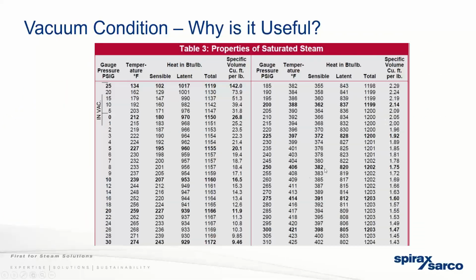So vacuum condition, why is this useful? So here's a steam table. It's going from vacuum up to 30 PSI. The table would look pretty similar even if we went up to 150 PSI. The latent heat is the energy used for heat transfer in the steam. The higher the pressure, the lower the energy, so the lower the latent heat. And you can see as you go into vacuum, it continually increases. So at 20 inches of vacuum, we have around 1,000 BTUs per pound of steam. So that's the energy content of that steam. If we were operating at an atmospheric type of system where we're allowing air into it, you can see the energy difference. So there's a loss of efficiency by operating at atmosphere instead of vacuum.